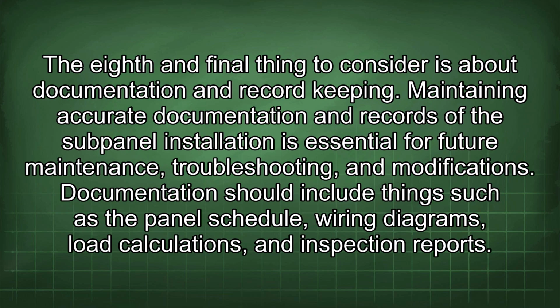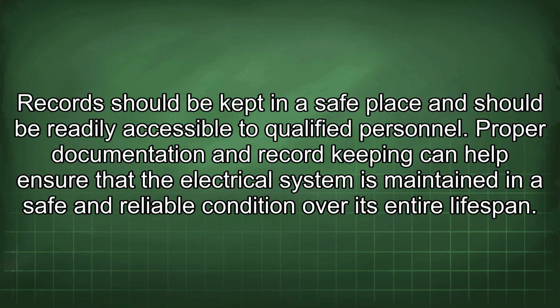The eighth and final thing to consider is documentation and record keeping. Maintaining accurate documentation and records of the subpanel installation is essential for future maintenance, troubleshooting, and modifications. Documentation should include things such as the panel schedule, wiring diagrams, load calculations, and inspection reports. Records should be kept in a safe place and should be readily accessible to qualified personnel. Proper documentation and record keeping can help ensure that the electrical system is maintained in a safe and reliable condition over its entire lifespan.